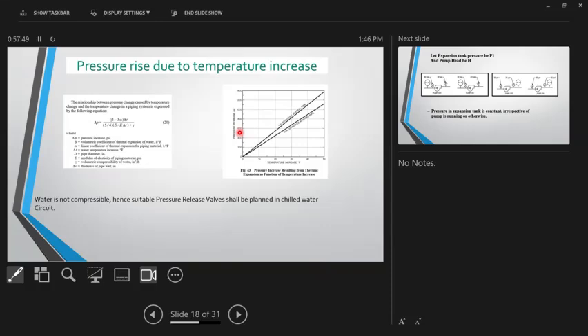If it is a small building, you are not going to design it for PN 40, PN 60, correct? You are going to design it for PN 20 or PN 10 or PN 16. So a simple 1 inch line can have a pressure increase up to 41 bar. So what it means is it will break, correct? Because it is not designed for that.